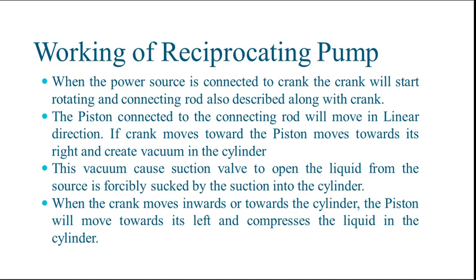Let us understand the working of reciprocating pump. When the power source is connected, the crank will start rotating along with the connecting rod. The piston connected to the connecting rod will move in linear direction. If the crank moves outwards, the piston is going to move towards its right and it creates a vacuum in the cylinder. This vacuum causes the suction valve to open and the liquid from the source is forcefully sucked by the suction process into the cylinder.